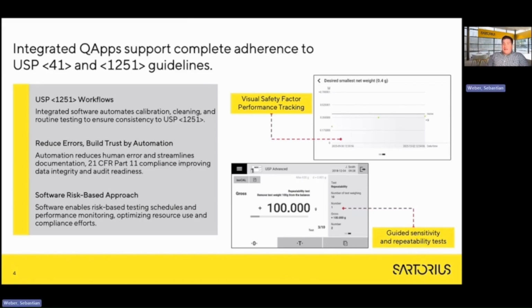For this, on our Sartorius balances, we have a concept called QApp. These are very small applications that represent a specific weighing task and run directly on the balance, and can be operated via the balance screen by the users. They guide the user through the specific task, they can observe what the user is doing, they can evaluate results, and then also create electronic documentation that is 21 CFR Part 11 compliant. For example, here you see our USP Advanced QApp on the screen.